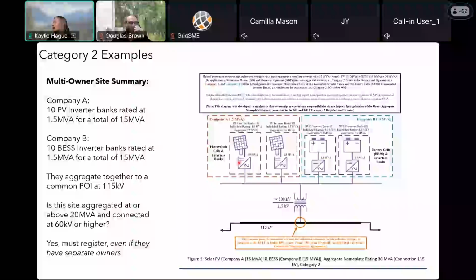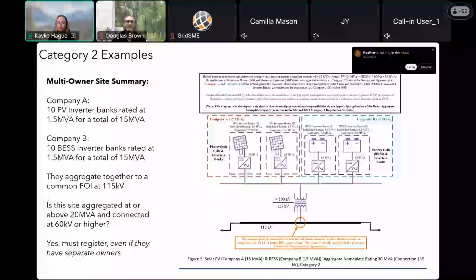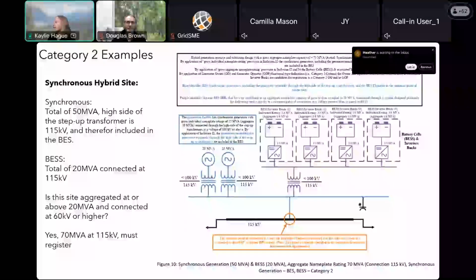So company A owns the PV portion, exact same setup, 10 inverter banks, each rated at 1.5 MVA. So that's a total of 15 MVA. And we've seen people say, well, I don't meet the categorization because I'm at 15 MVA, I'm not at 20. But you're aggregating with company B, who owns the battery storage, and this is also 15 MVA. So together, you're connecting at 30 MVA with the high side voltage of 115 kV. So yes, you must register. Even if you are separate owners, you will each be required to register.